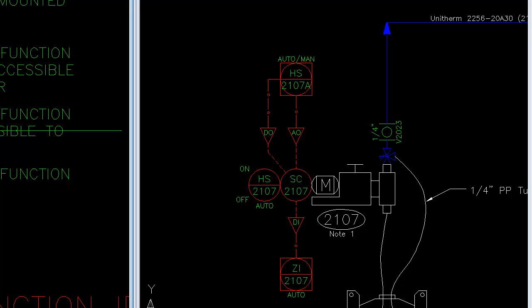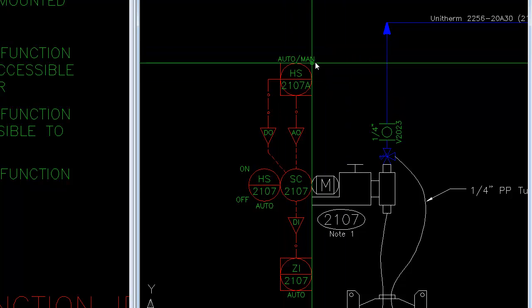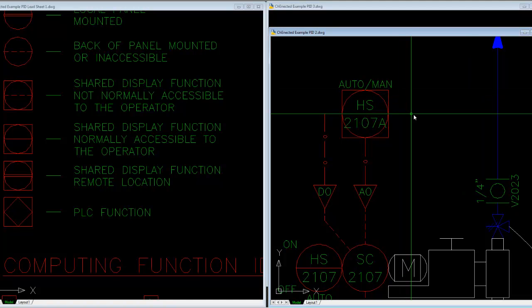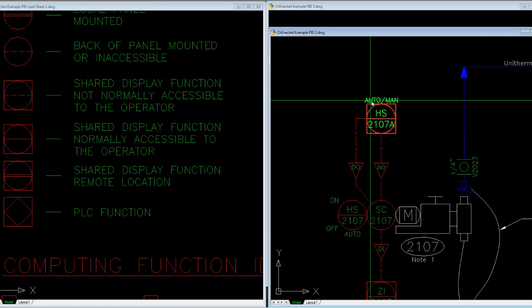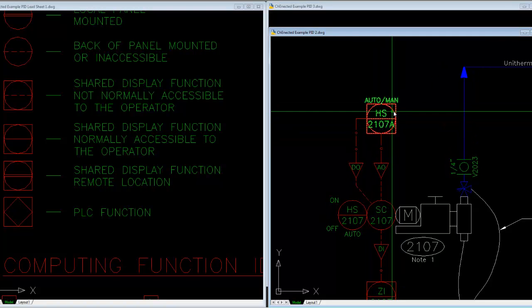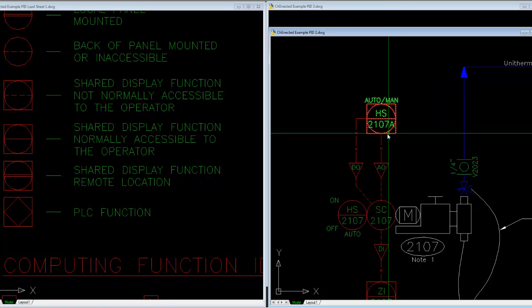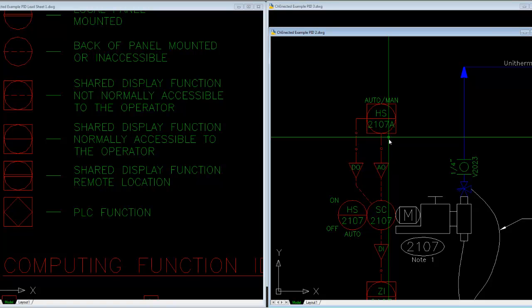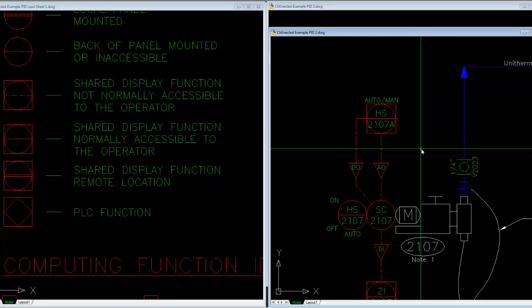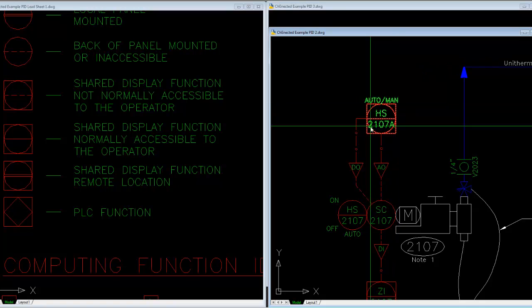A good example of the square and circle would be — moving over to the example P&Is I provide — a hand switch on a computer screen. You would potentially have the ability to click a button that said start or stop the pump, or place the pump in auto mode or manual mode. This block with a circle through it would actually represent a button on a control screen that you clicked, or some other graphical item that abstracted a switch, lever, or button that you would normally push to start and stop a motor in the field.